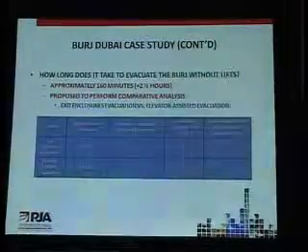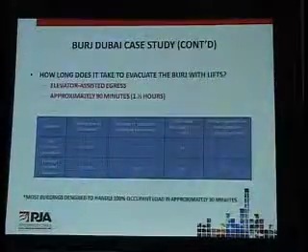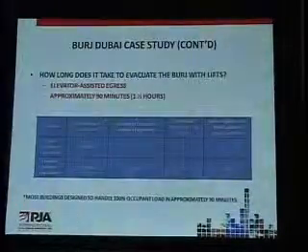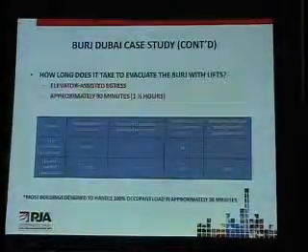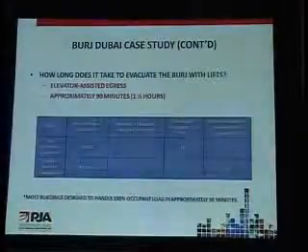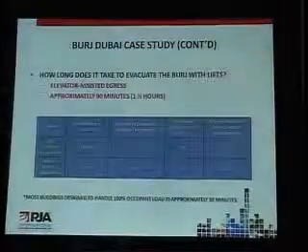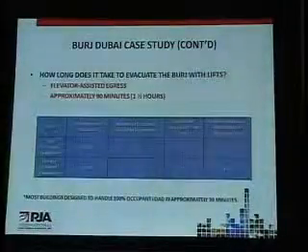So we went through and we did the comparative analysis employing elevators in conjunction with using stairs, and we were able to reduce the evacuation time by almost 50%. So we're really looking at about an hour and a half evacuation time.